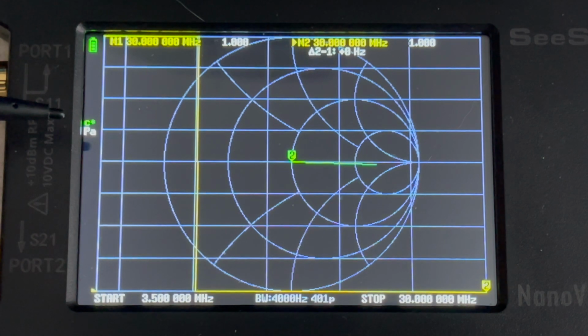Okay, and the display will show figures from C0, C1, C2, C3, C4. This would correspond to the calibration data that is loaded. An E indicates an enhanced response calibration is enabled. Not that you need to be aware of it, but it helps to understand what it means. And there's another one, SOLT, which indicates that the corresponding short, open, load, and through standards have been measured. So that would suggest you should see at least that in there after you calibrate.